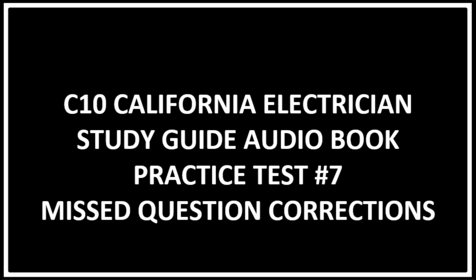Question 89. Healthcare, patient care area, exposed metal raceways not to exceed 500 mV difference at frequencies of 1000 Hz or less across 1000 ohm resistance. Health, patient care areas, not to exceed 500 mV differences for exposed metal raceways.